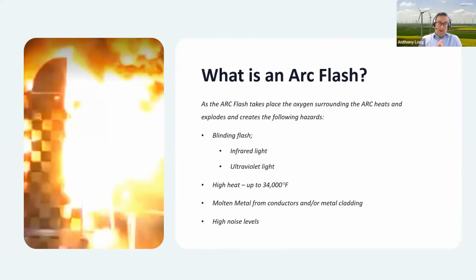When we talk about arc flash clothing, it's protecting you initially from the actual heat that's generated with the arc itself, but the secondary protection with the arc flash clothing comes from molten metal. So if any of you are working in metal foundries, you'll know that molten metal carries a massive amount of heat. When it starts to cool down, it sticks very easily to garments, and you've got a secondary heat source stuck on the garment, burning through the fabric to the wearer on the inside.